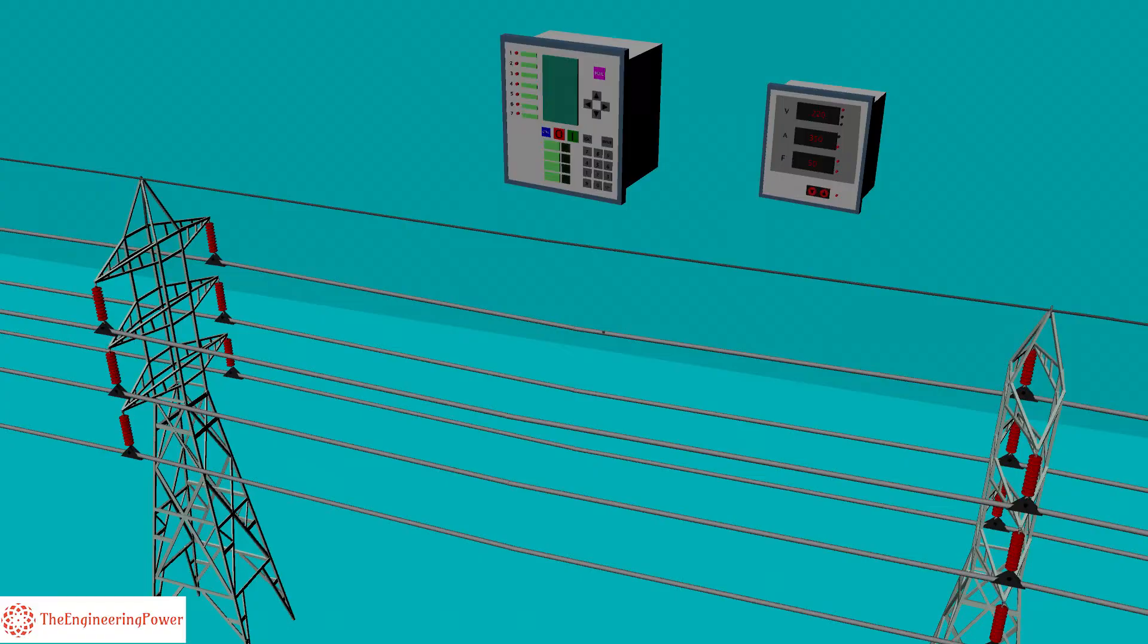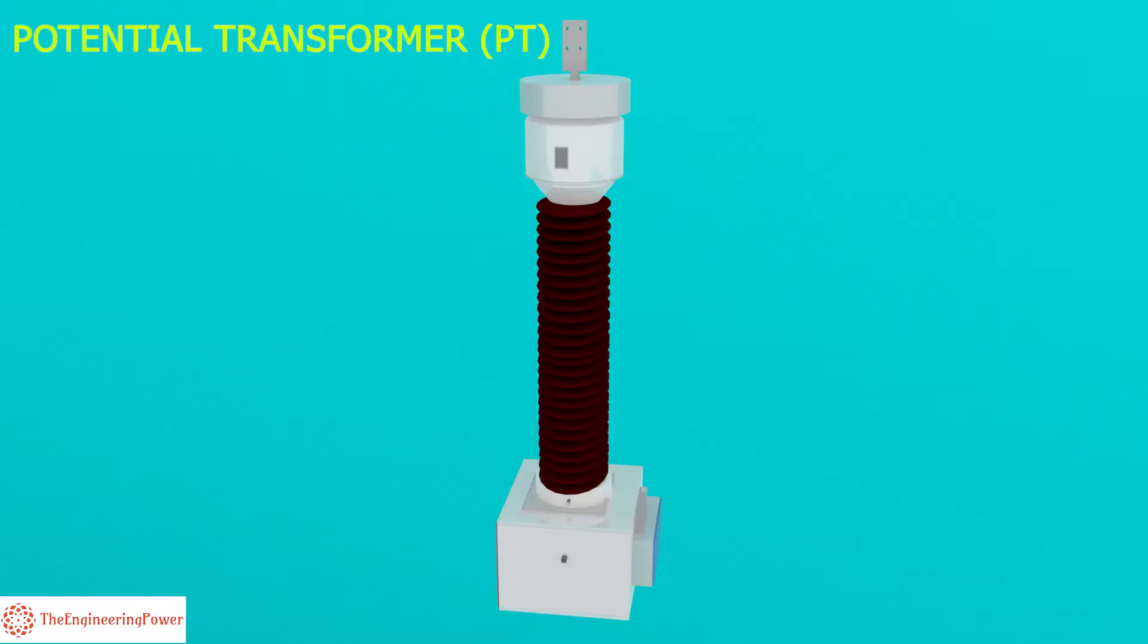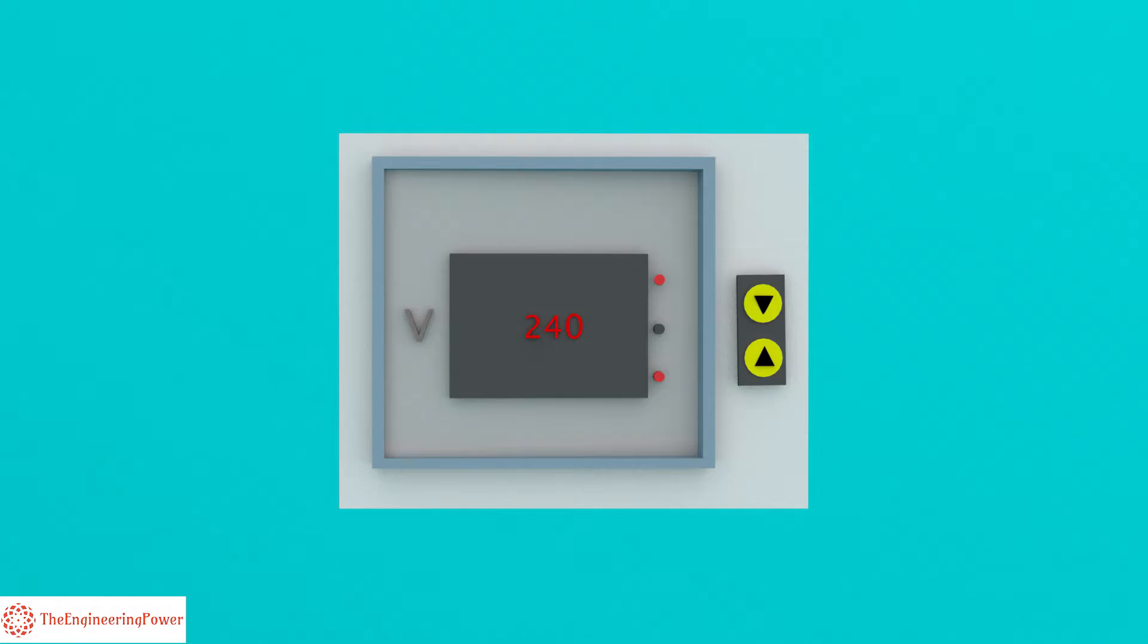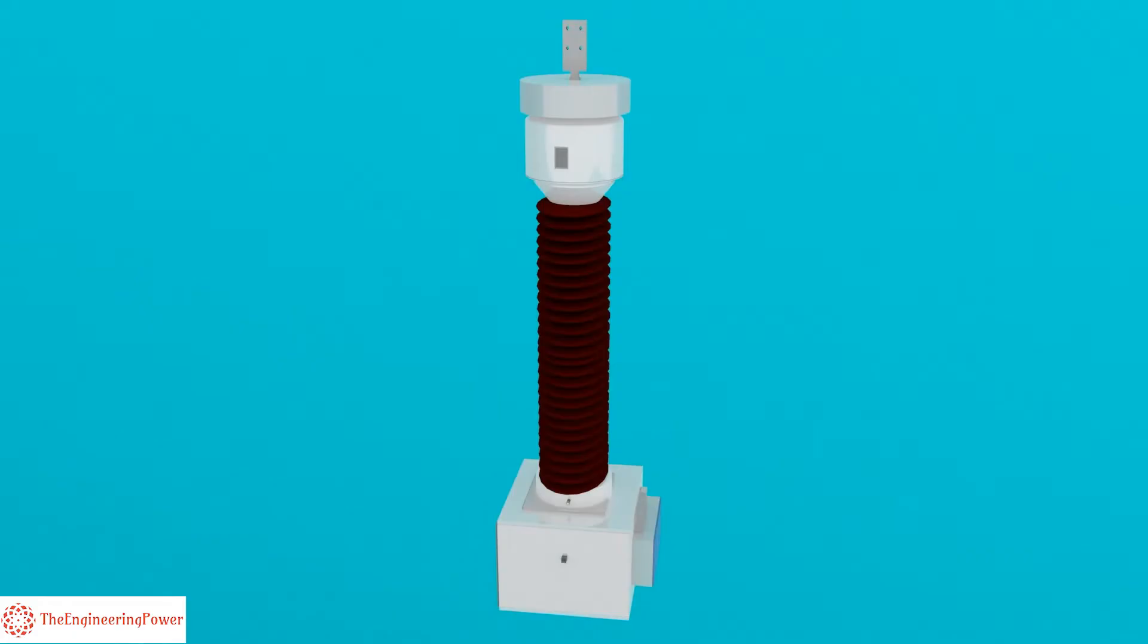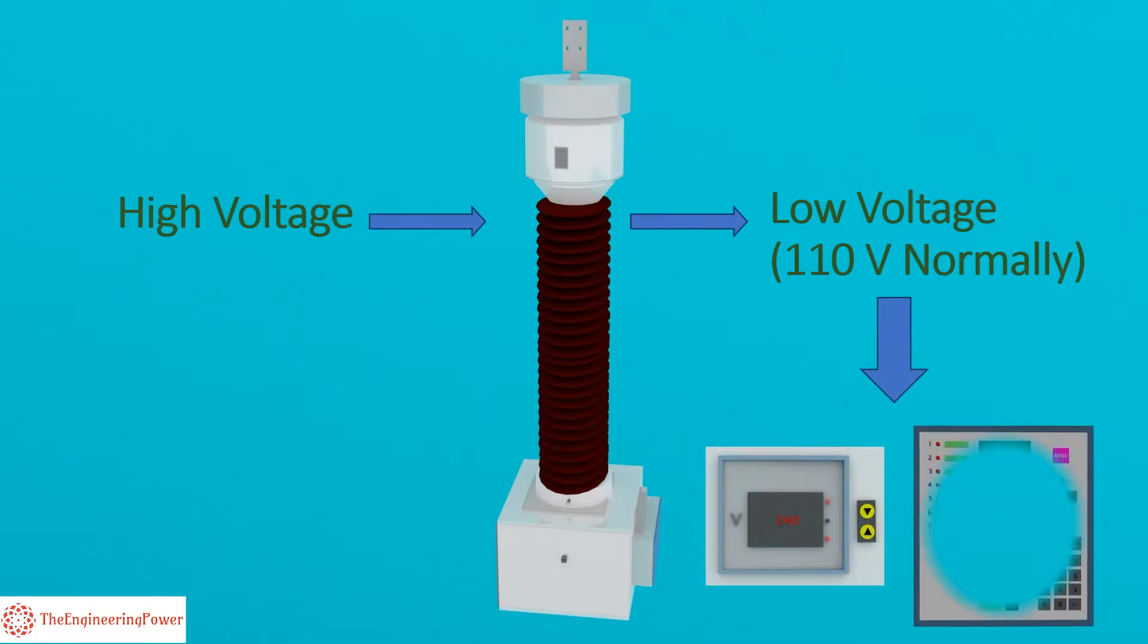This special transformer is called a potential transformer or simply PT. Standard voltmeters can then be used to measure this voltage. PT transforms voltage to safe value, normally 110 volts. This voltage can be fed to low rating meters and relays in the control room.